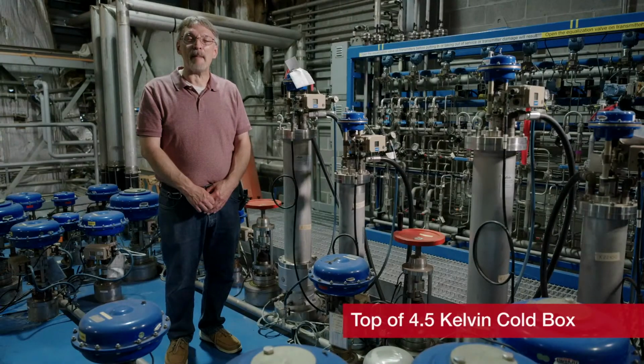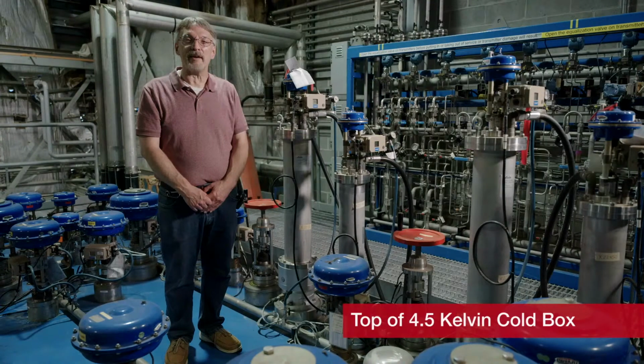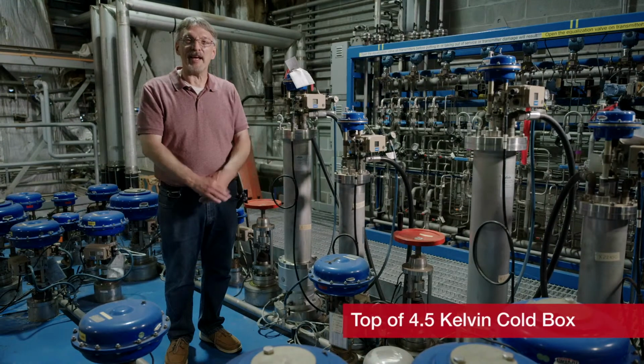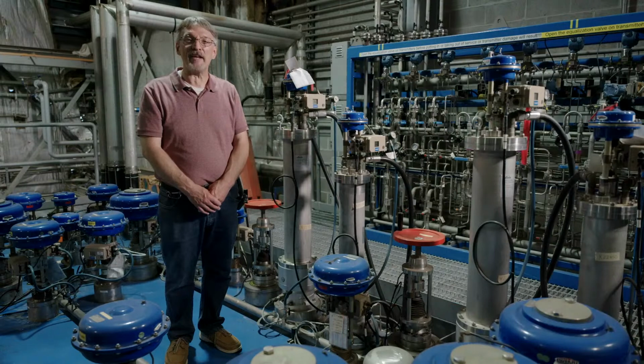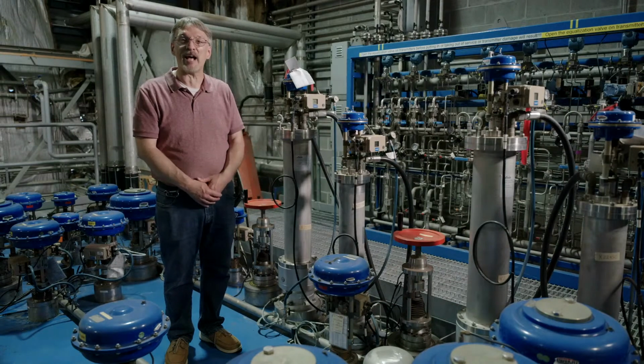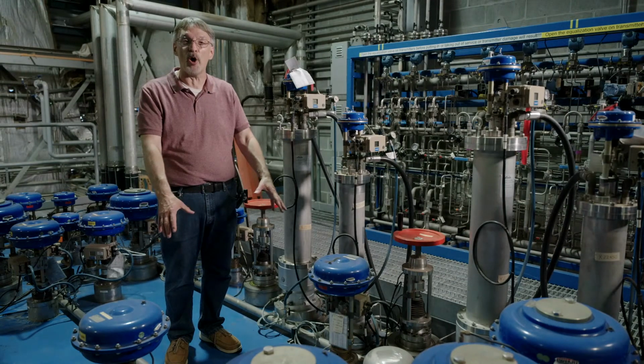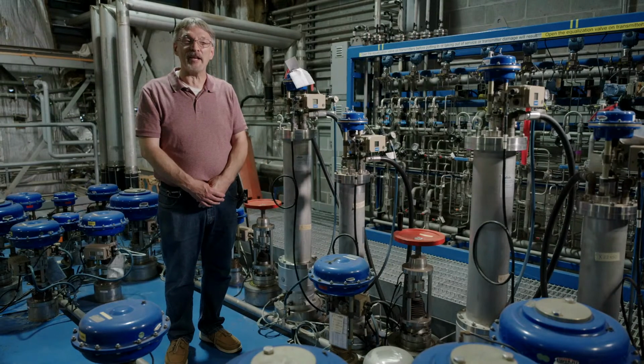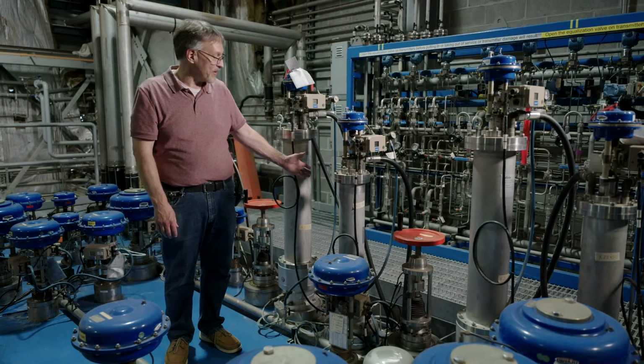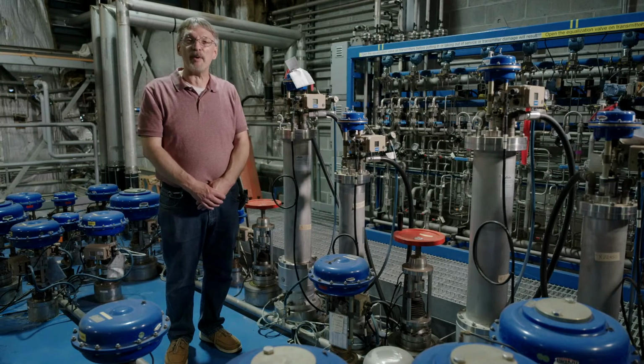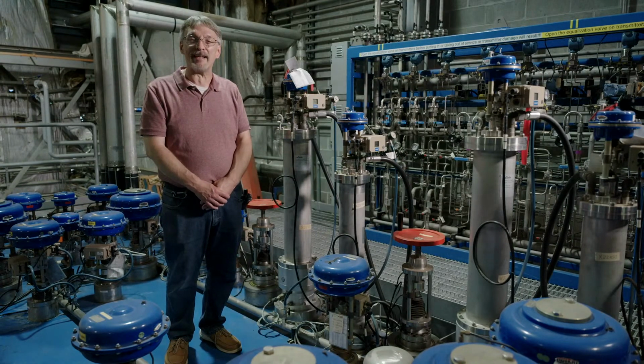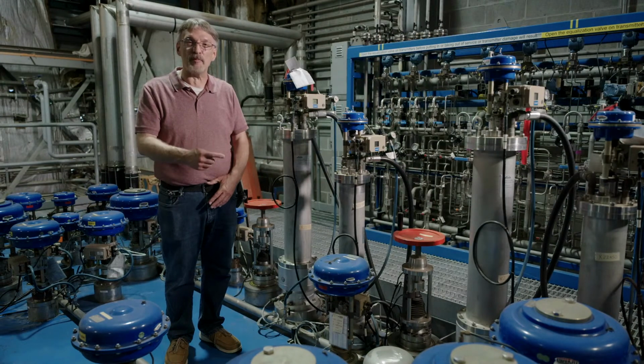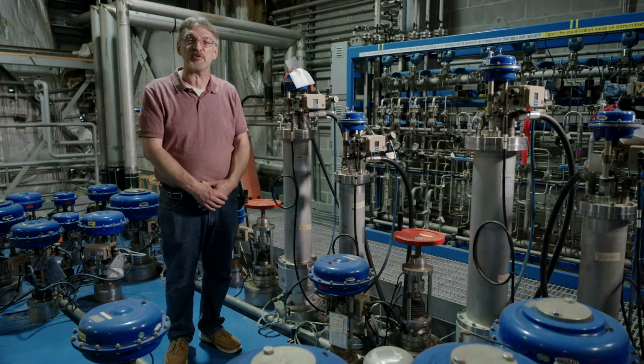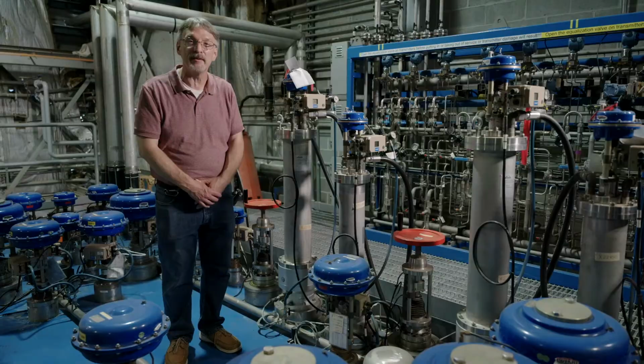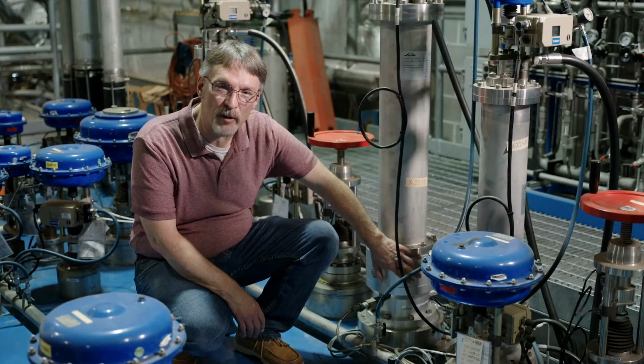Now we're on the refrigerator. This contains valves that control the flow of helium around the heat exchangers that are inside of this box below. They also control the flow of helium into turbo expanders like these here. These turbo expanders take high pressure helium and spin a turbine wheel that expands the gas and lowers its temperature. This is a cryogenic expansion turbine.